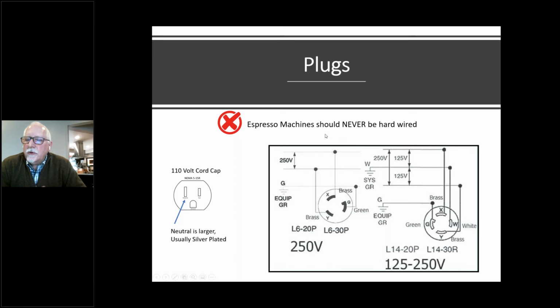If you have a commercial espresso machine and you've got a 4-wire hookup and you don't have a neutral, I think it is acceptable to hook up the ground and the X and the Y and just leave the neutral disconnected because you're not using it. It's not going to impact the machine, and it's not going to pose any hazard to the building or the equipment. Any questions? Matt, Kurt, you have anything?